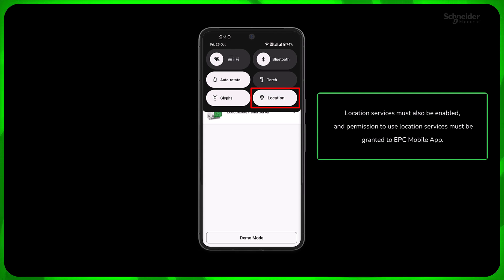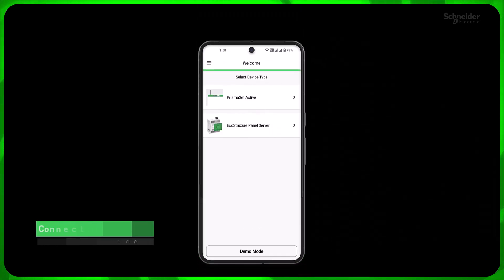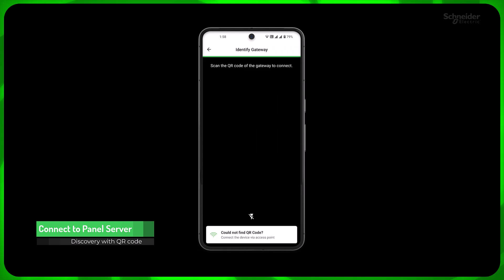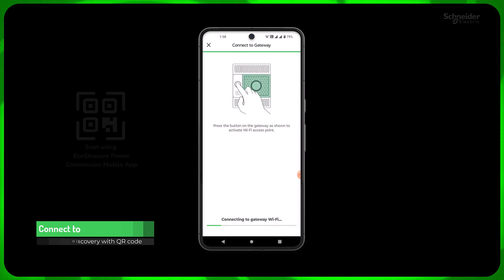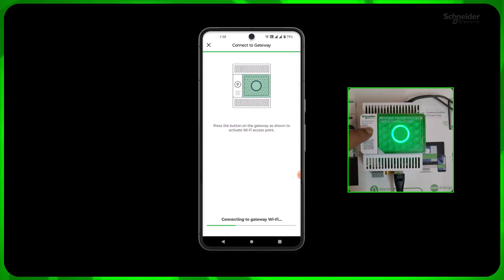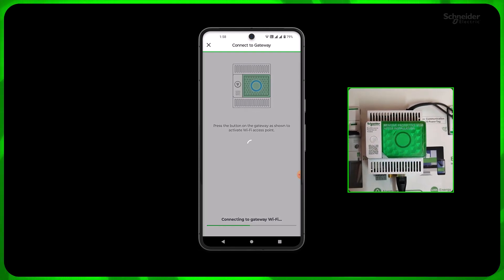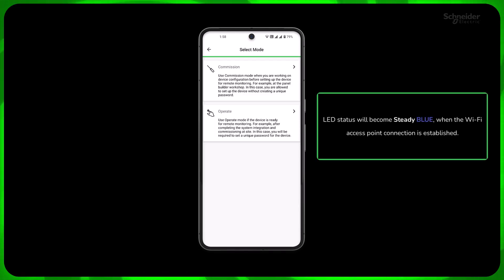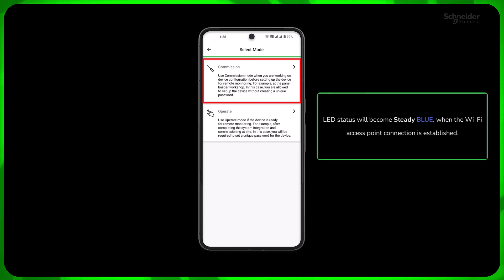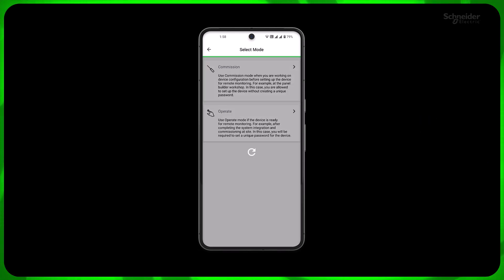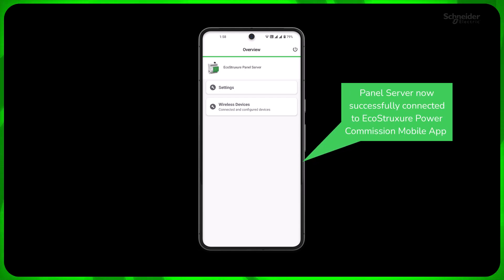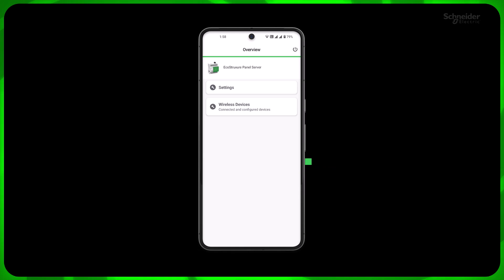Once you log in, select EcoStruxure panel server from the list. Scan the QR code on the panel server. Press the panel server front button for less than 5 seconds to activate the Wi-Fi access point. The panel server front LED should be blinking blue. Select the commission mode — you will reach the overview screen. Your panel server is now successfully connected to EcoStruxure Power Commission mobile app.